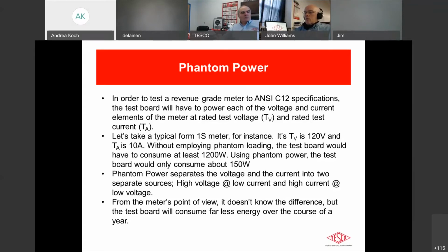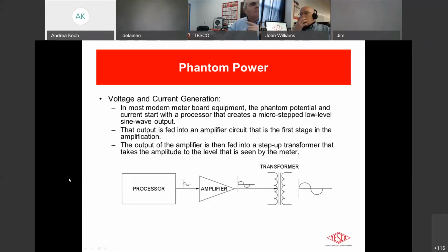One is a high voltage source, and it's at very low current. So again, the power output on that channel is very low. And then high current at very low voltage. Again, a low power situation, but you combine the high voltage and the high current and apply that to the meter. From the meter's point of view, it's a real loading condition. And that's really what we want to test for. So how do we do that?